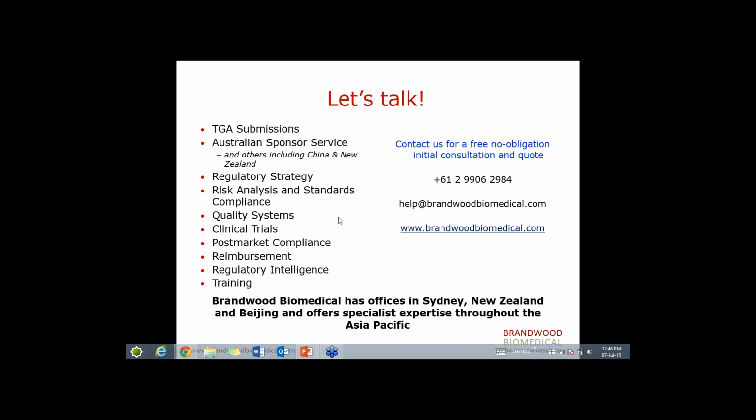Okay, there's one that says, what is the length of time for technical file review? So for devices, if you're registering a product based on CE certification, there's actually no re-review of the technical file. So as long as the annual fees are paid and the notified body is undergoing these reviews, you don't actually need to do anything with TGA. However, once the notified body does review the technical file, they will usually reissue a CE certificate, and especially if it expires or something, that must be notified to TGA by means of a variation to manufacturer's evidence. For some classes that are high risk, this can actually trigger another application audit if there's an expired CE certificate sitting on file for a particular device.